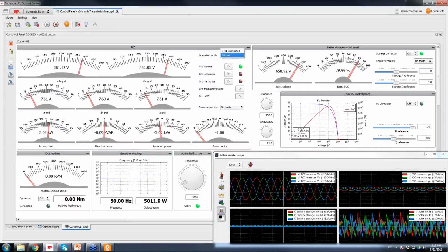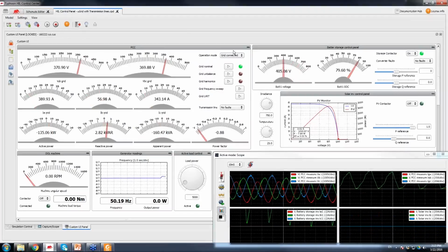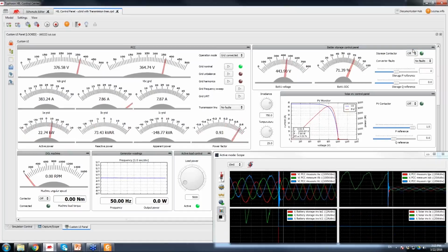Let's now switch back to the grid. You can see that this switch crashed our controller and it's not able to connect back to the grid. So this is again one perfect example of how these kind of tests bring benefits comparing to testing in the actual power line. So now when we turned off the controller, you can see that the grid is again stabilizing.